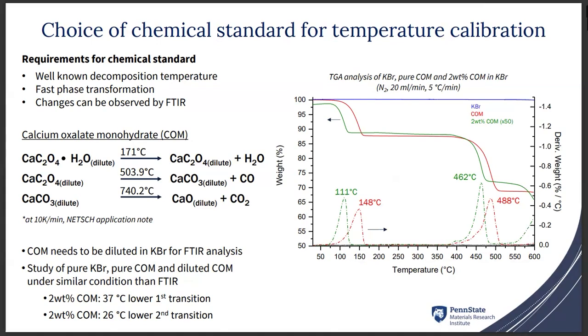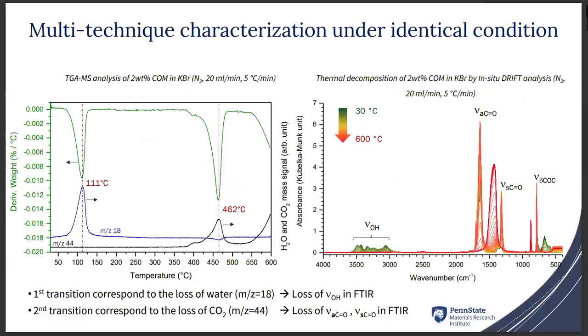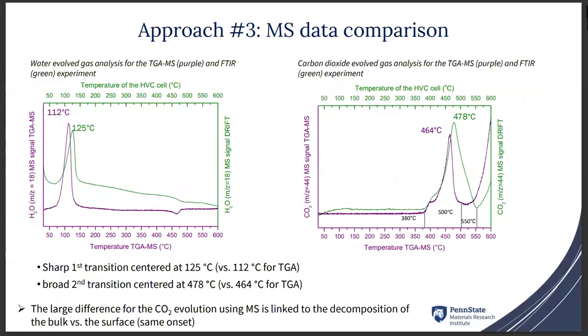Yeah, thanks for the talk. What about temperature variations across the sample itself? Are some of the transitions that you see there broadened because different parts of the sample are actually at different temperatures? This is correct. This is even better viewed in the MS data. So we have exactly the same shape of the carbon dioxide signal, except that for the TGA, I use 8 milligrams of sample. For the FTIR, it's more in the order of 30 milligrams. And that's why you have exactly the same signal, but it's broadened.